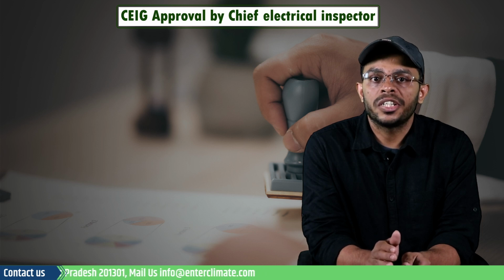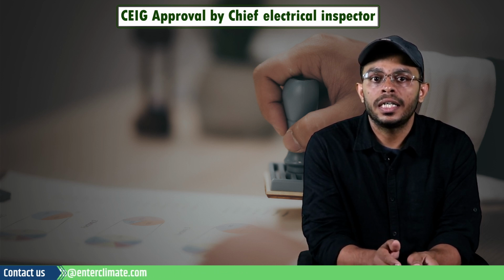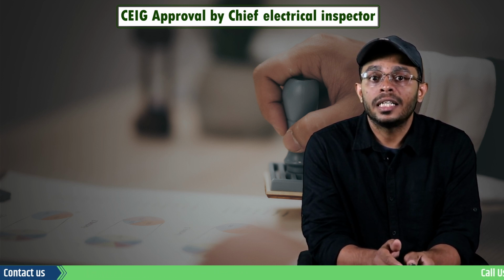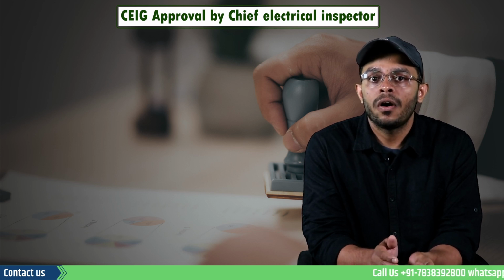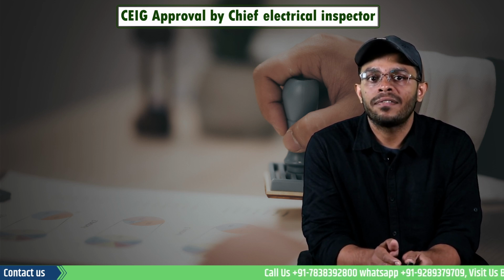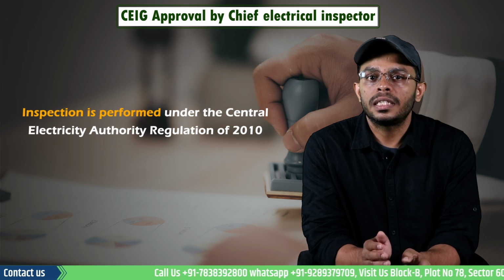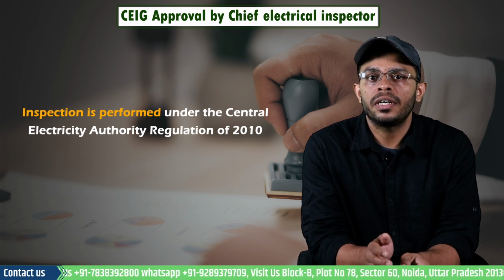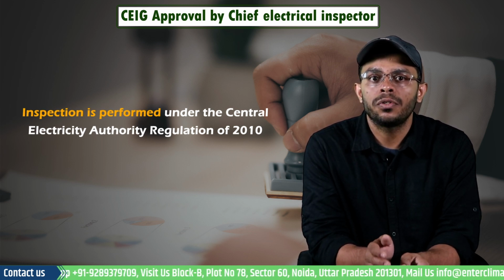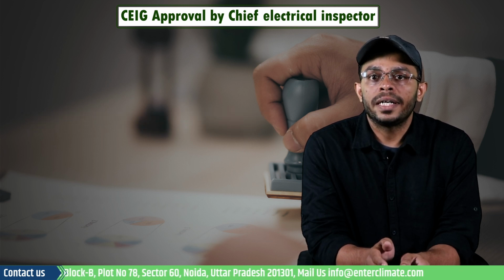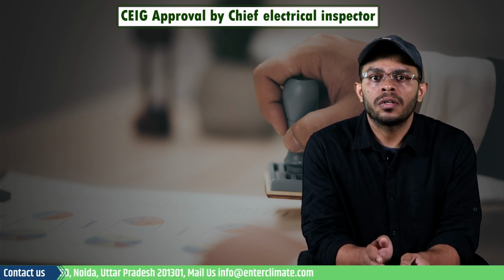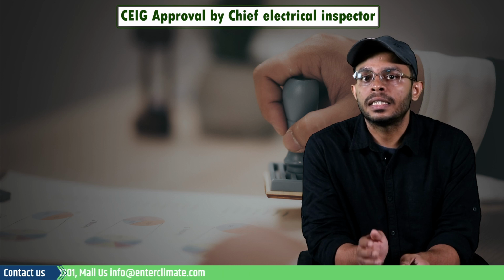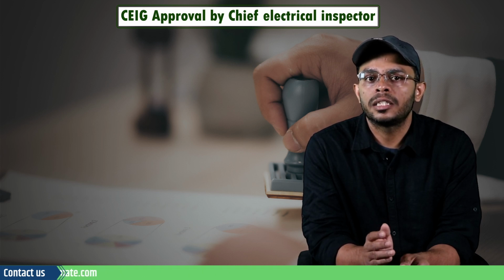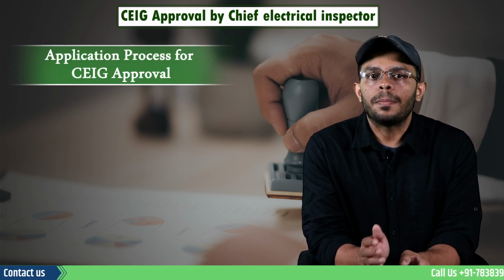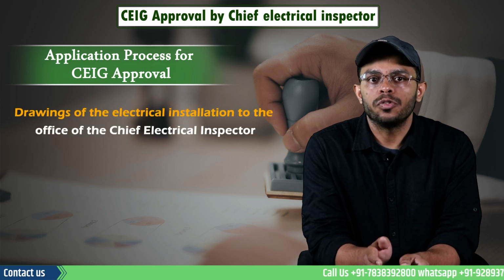Thereafter, a site inspection is carried out under Regulation 30 or Regulation 43, that is before the commencement of the supply or the recommencement of the power after shutdown for more than 6 months. This inspection is performed under the Central Electricity Authority Regulations of 2010. The completed electrical installation work must undergo inspection by the concerned officers of the Electrical Inspectorate Department. Let's see the application process for the CEIG approval.